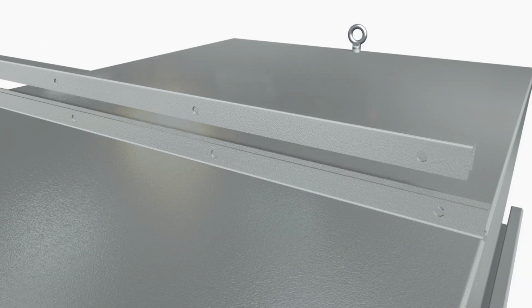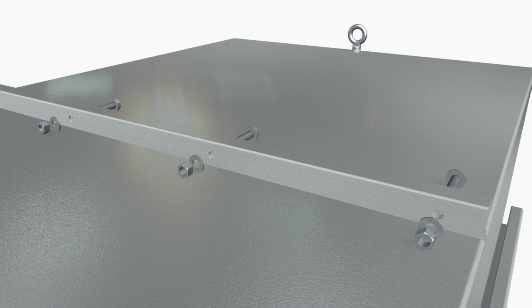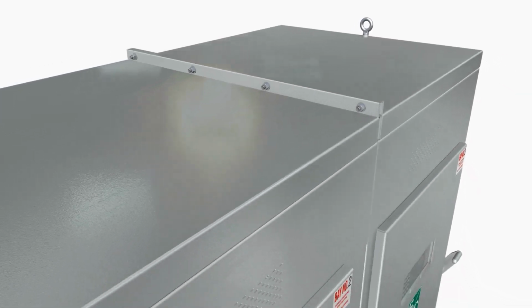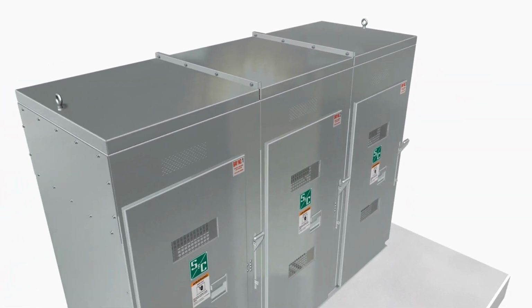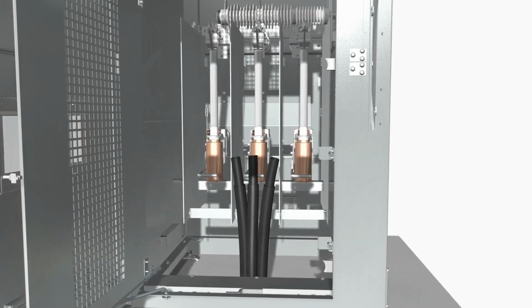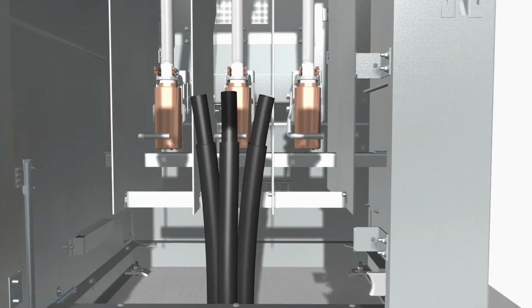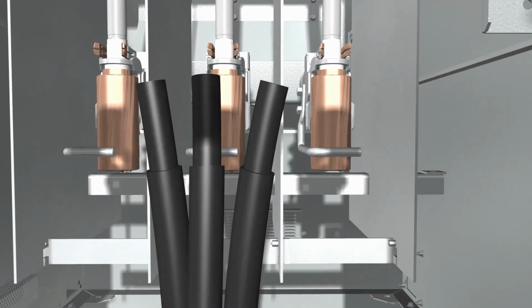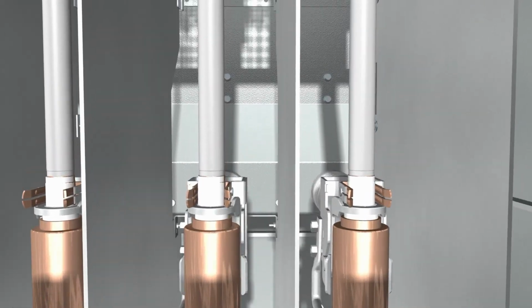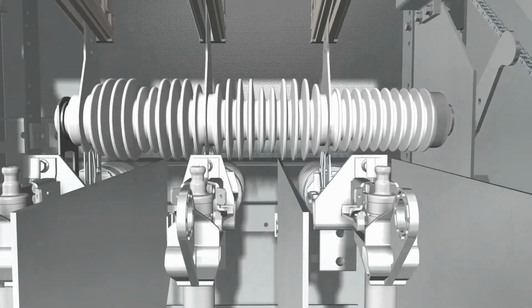On 25 kV and 34.5 kV outdoor and drip-proof designs, after all bays are in place and bolted together, install roof caps over roof flanges between bays and bolt them into place using the hardware furnished. Step 7. Remove all barrier braces and switchblade tie cords installed to restrain movement of these parts during shipping and handling.